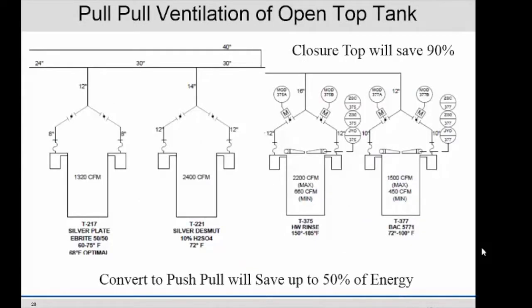This is an example of a new design for a new system, not by us. We would have done it differently. They're leaving some of the tanks open. Don't open the tank. Put closures on them so you can reduce that ventilation. So they're having to do, like right here, 2,400 CFM. If they close that top, if they put a top on it, it would only need to be 240 CFM when it's closed. And most of the time, they don't use them. They'll have 150 tanks and they're using one tank. So why not close all the other tanks that you're not using? These have closures, but they're only reducing their consumption in half, on some of these. Or a third. Well, you can go down to 1/10. You don't have to go just to 1/3. You don't have to be that conservative. So there's a lot of places to save energy.